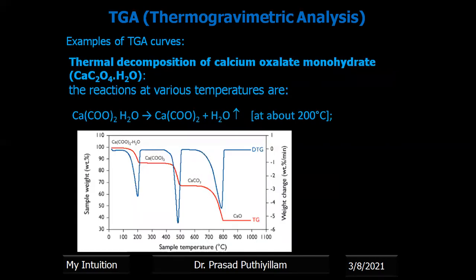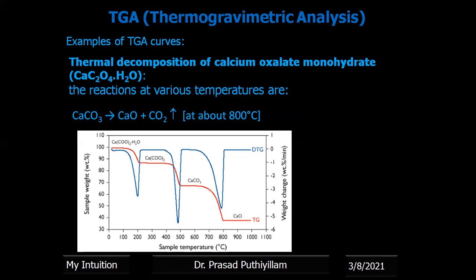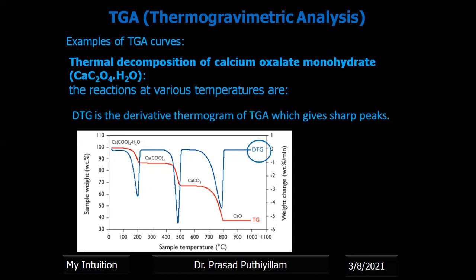Another example is the thermal decomposition of calcium oxalate monohydrate (CaC₂O₄·H₂O). At around 200 degrees Celsius it loses the water of hydration. At around 500 degrees Celsius it loses carbon monoxide to become calcium carbonate. At around 800 degrees Celsius the calcium carbonate further decomposes to give calcium oxide with removal of carbon dioxide gas. In this thermogram, the red line indicates the TGA curve and the blue line represents the derivative thermogram, which gives sharp peaks to easily identify the exact temperature at which decomposition or weight loss occurs.